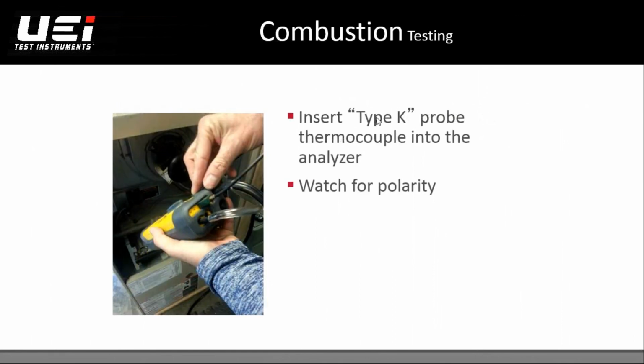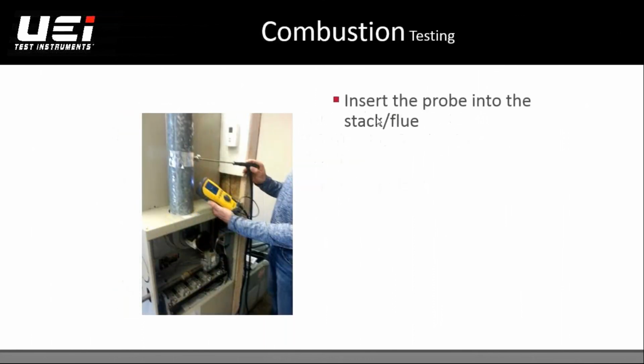Then there's a K-type thermocouple that you're going to plug into the T1 port. It's important - I've seen it happen, I haven't been able to quite do it myself - but you want to make sure you're watching for the polarity. When you look at that K-type thermocouple, make sure the small end is plugged into the small hole and the big end into the big end. Don't force it; it should slide in easy if you have it ready to go.